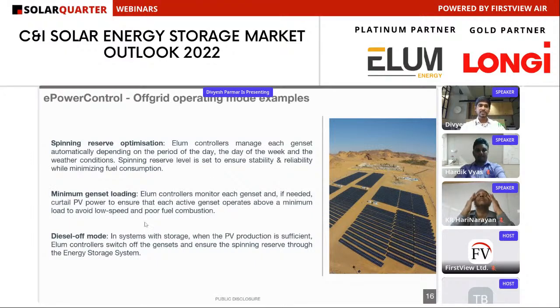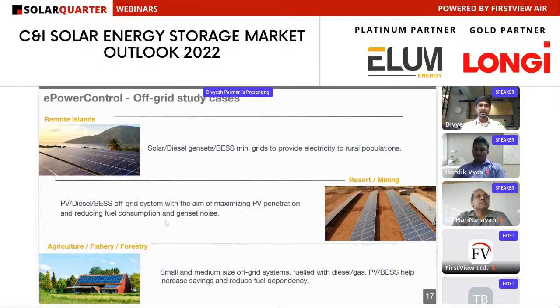The next feature is the minimum genset loading, meaning that when you are doing the solar diesel integration, we are running gensets at minimum 30% loading or at the percentage loading recommended by the DG OEM. And when you are running with the solar DG and the storage plants, basically we turn off the diesels when the battery state of charge is high. And if the SOC level falls, then we can run the solar DG and batteries together. You will find the applications of the off-grid at remote islands such as Leh, Ladakh or Andaman and Nicobar in India. You will find the applications with resorts, mining projects or agricultural projects.